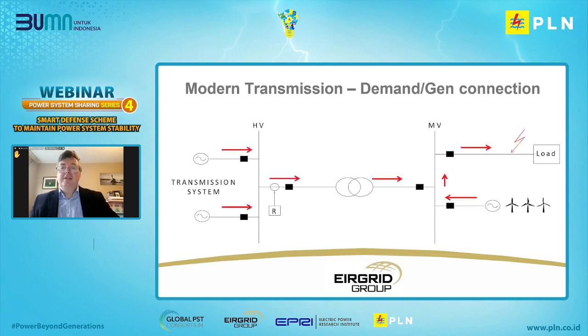Sorry, advance again. So what we've got now, in the modern setup, is both load and generation connected on the distribution system. If there's a fault in the distribution system, obviously there are contributions from the transmission system, which you can see coming from the left, and there are also now contributions from the distribution-connected generation resources. So this impacts our traditional overcurrent protection installed on the HV side. Next slide, please.